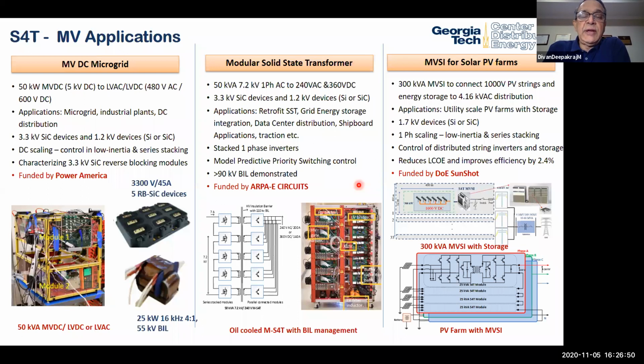So you have to have a 90 kV BIL that transformers are able to meet very easily through insulation design and coordination with the surge suppressor. With semiconductors, that's very, very challenging, but we've been able to do that. We've demonstrated 90 kV BIL on the converter and demonstrated high efficiency.